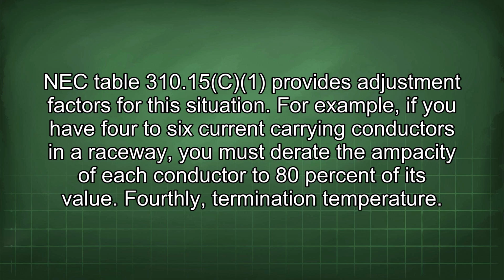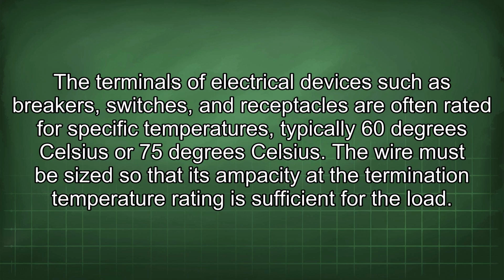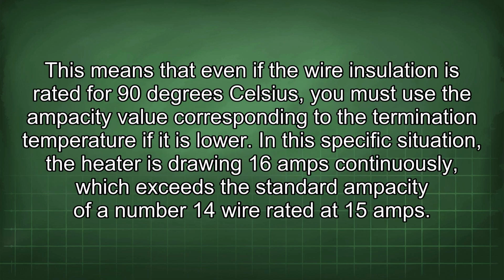Fourthly, termination temperature. The terminals of electrical devices such as breakers, switches, and receptacles are often rated for specific temperatures, typically 60 degrees Celsius or 75 degrees Celsius. The wire must be sized so that its ampacity at the termination temperature rating is sufficient for the load. This means that even if the wire insulation is rated for 90 degrees Celsius, you must use the ampacity value corresponding to the termination temperature if it is lower.